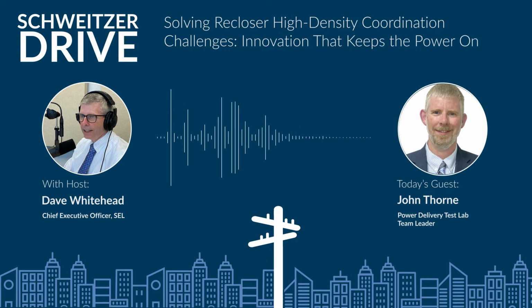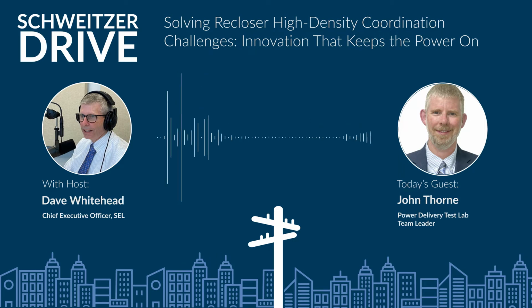That's why we talk about lockout coordination, making sure we lock out the device closest to the fault. We hold that in very high regard, because it can really turn into a circus in a hurry when you start presenting confusing information to our operations center and the troublemen in the field. So that non-communicating high-density coordination has proven very valuable in parts of the state where we haven't yet deployed the fiber optic communications required for the other method.